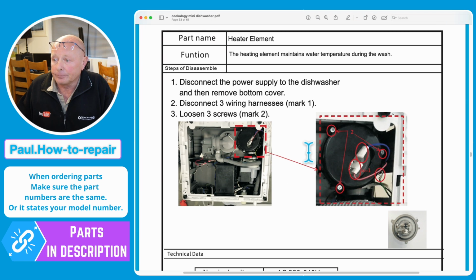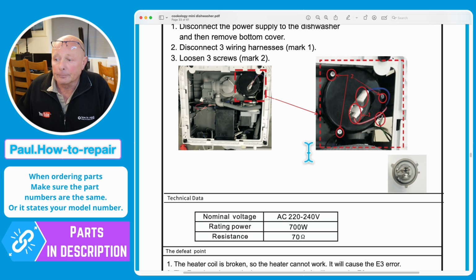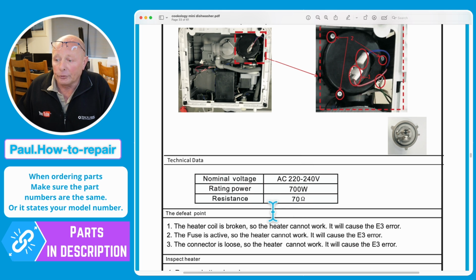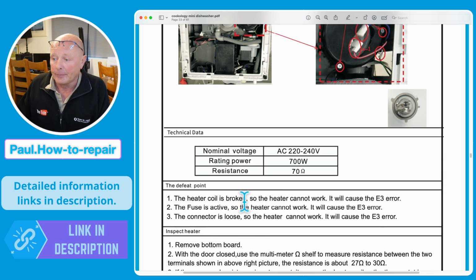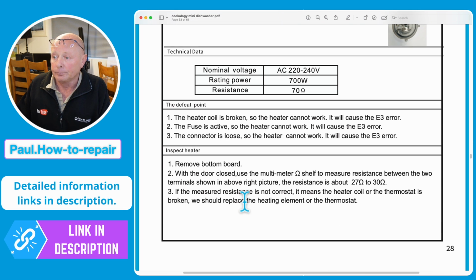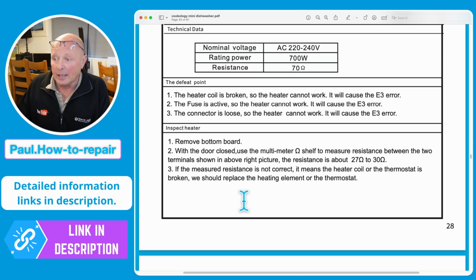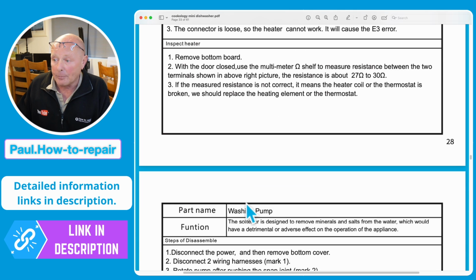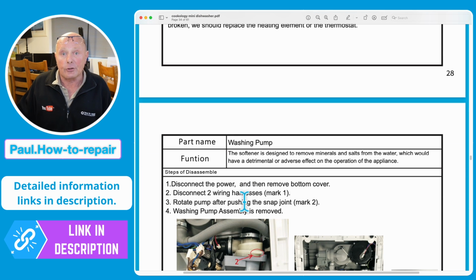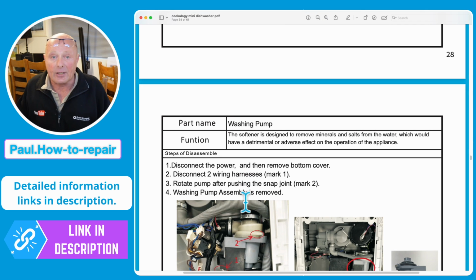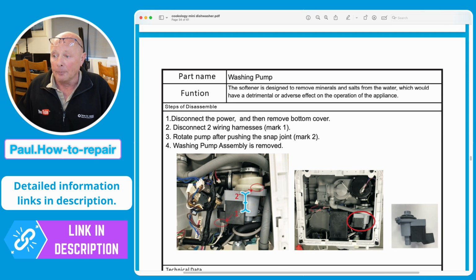Heating element, 700 watts, so you should have 70 ohms worth of resistance if the element is in good condition. There are also a couple of thermostats built into the actual heating element plate, which you will need to check. There are lots of videos regarding individual components on the website to assist you in checking things like NTC sensors, pumps, heaters and so on.